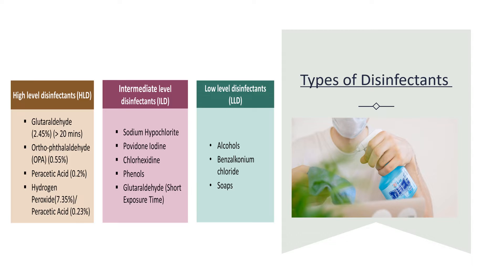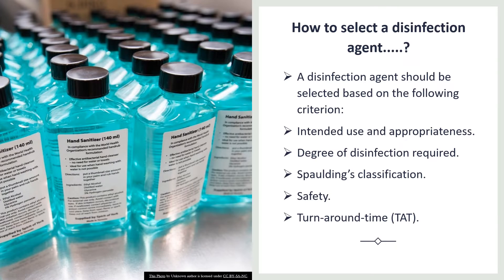High-level disinfection examples include glutaraldehyde, peracetic acid, and hydrogen peroxide. Intermediate-level disinfectants include sodium hypochlorite, iodine, and chlorhexidine. Low-level disinfectants include alcohols and quaternary ammonium chlorides. When selecting a disinfectant agent, it should be selected based on intended use, the degree of disinfection required, the Spaulding classification of the instrument, and safety considerations.